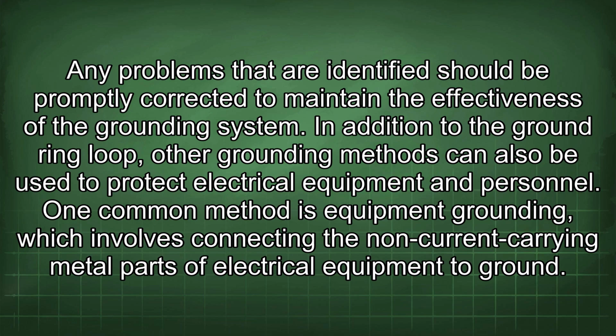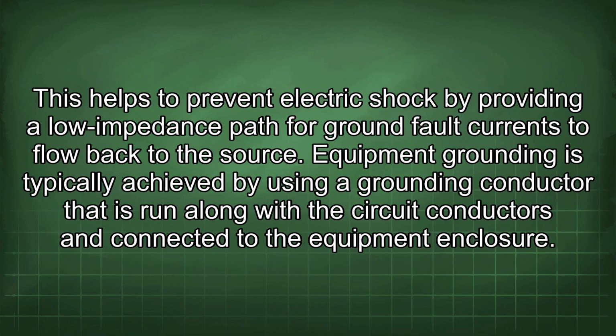In addition to the ground ring loop, other grounding methods can also be used to protect electrical equipment and personnel. One common method is equipment grounding, which involves connecting the non-current carrying metal parts of electrical equipment to ground. This helps to prevent electric shock by providing a low impedance path for ground fault currents to flow back to the source. Equipment grounding is typically achieved by using a grounding conductor that is run along with the circuit conductors and connected to the equipment enclosure.